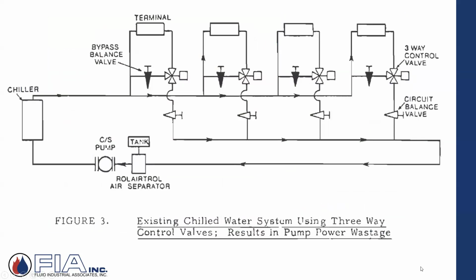So then the industry said, hey, how can we get away from that? Again, before variable speed, how can we move away from that? So one of the first answers was, what did they change here in the drawing? Yeah, we went from 2-way to 3-way. What's the benefit of that? Which gets us what? If you bypass? Constant flow. So you're not experiencing that movement backing up on the curve.